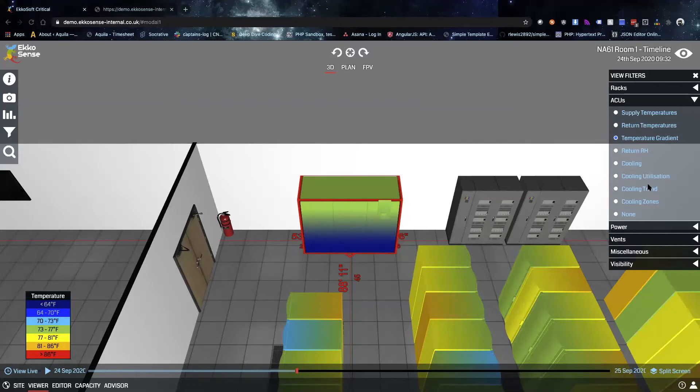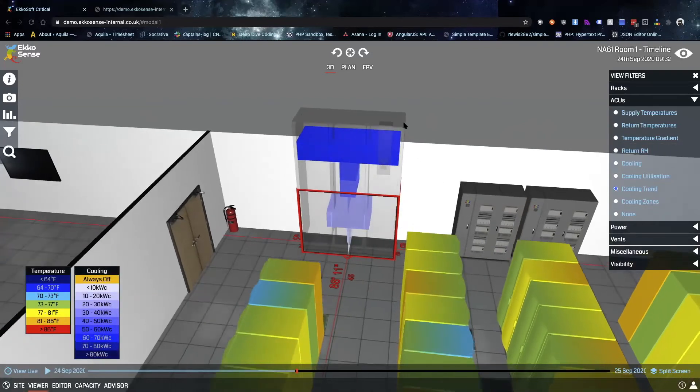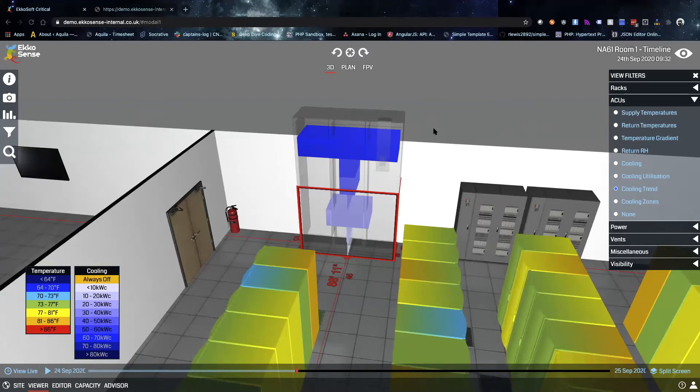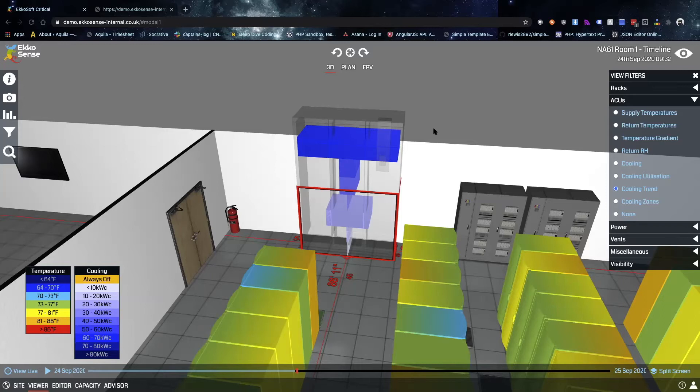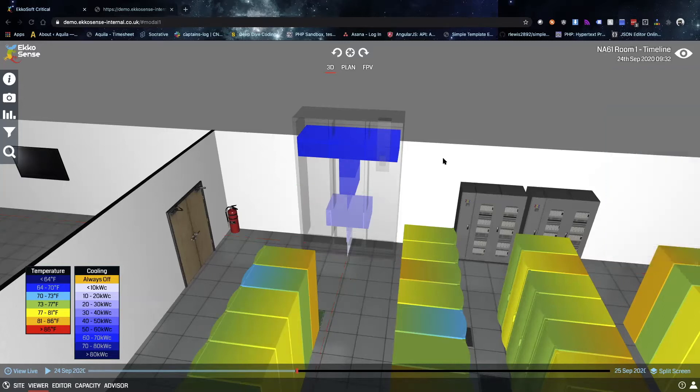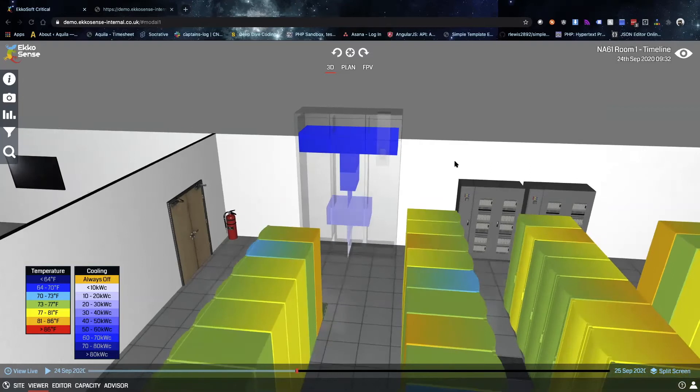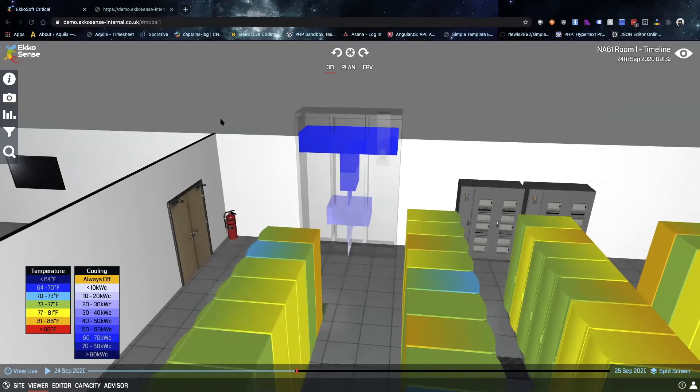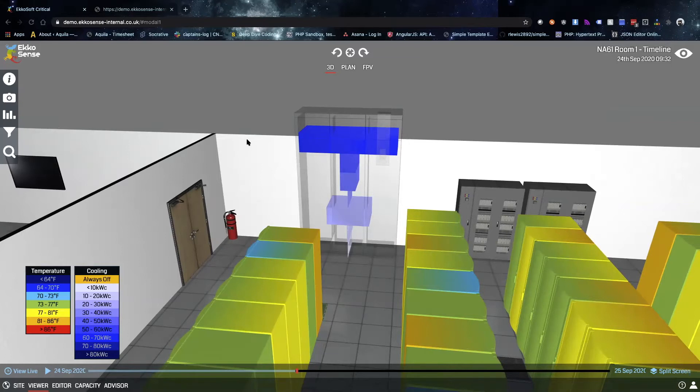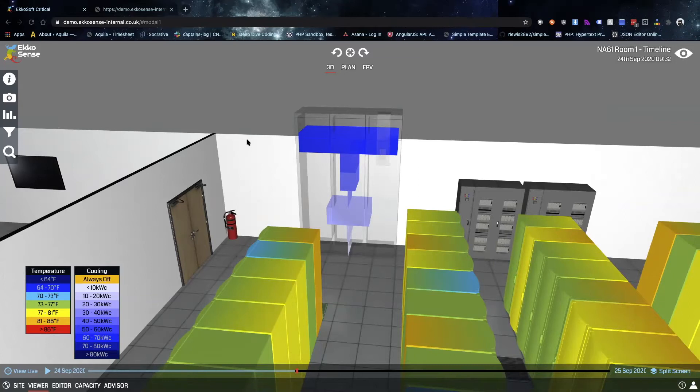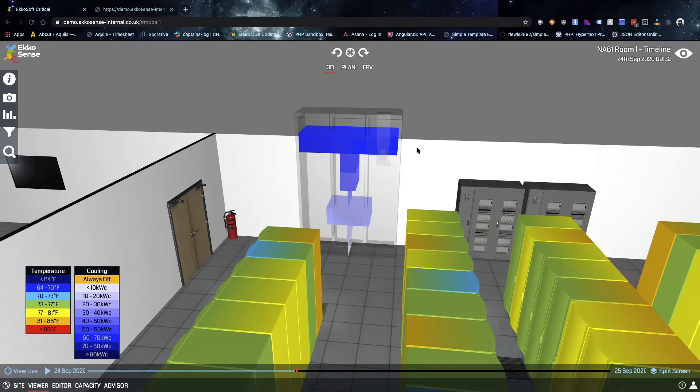Another really cool overlay that we provide is what we call the cooling trends. This is one of the exciting features made possible by the software. What we're looking at here is a histogram of this cooling unit's function over the last 24 hours. Each of these colors in this ghost image of the cooling unit represents a range of cooling delivered by that cooling unit, and the width of each of those bars represents the relative amount of time that the cooling unit was operating at that level.